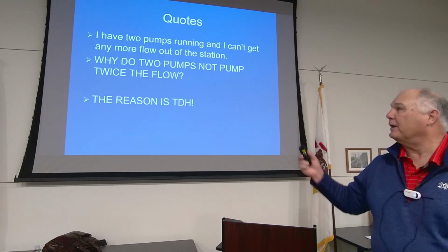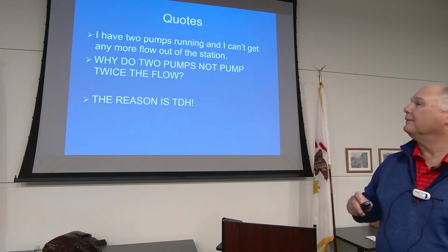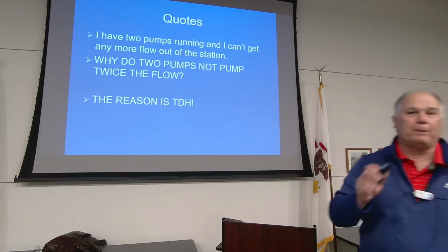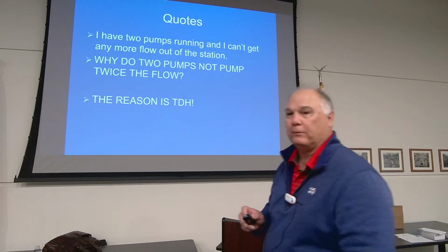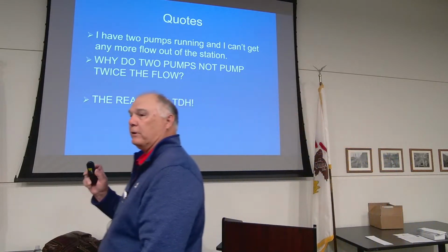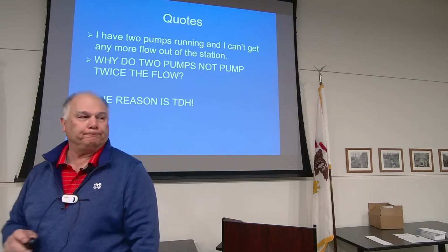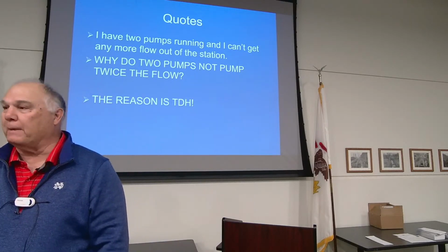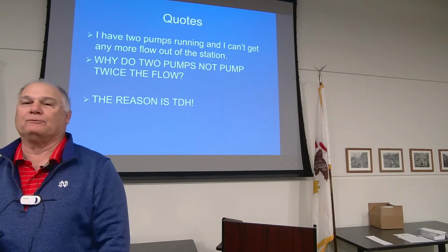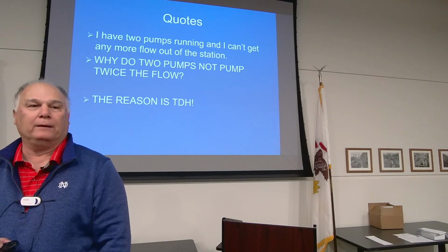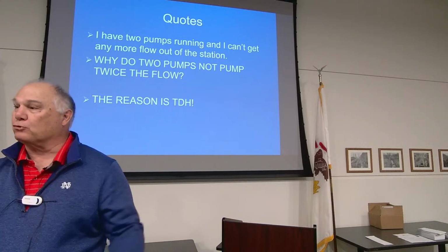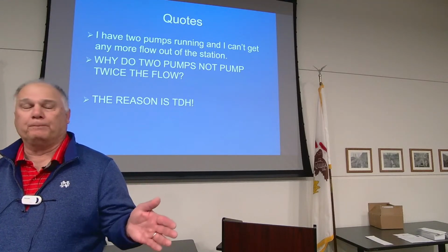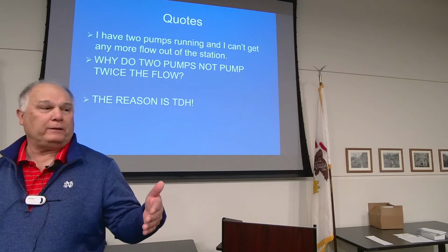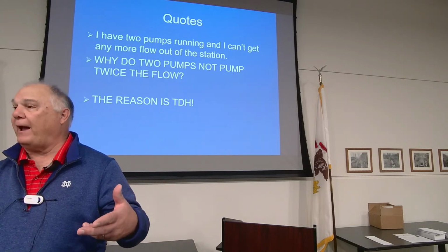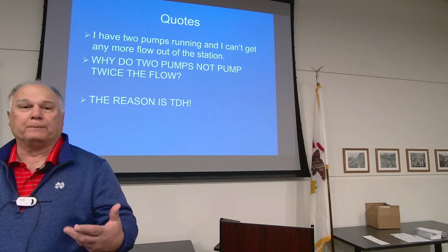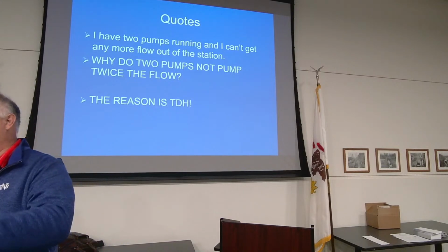Because, you guys can remember this, you can only pump so much poop through the pipe because the pressure goes up. And if the pressure goes up too high, you can't pump any more poop through the pipe. So remember that. If there's any that you remember out of this whole thing, remember that. Because if it's a short force main, you could pump a lot more flow. Long force mains, that force main is going to be your limiting factor on your TDH and what your pump capacity is, because that impeller can only put out so much water.